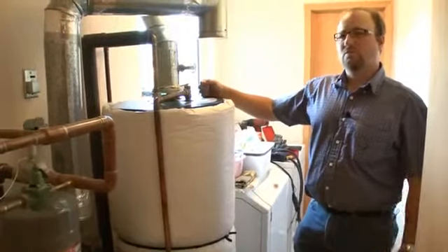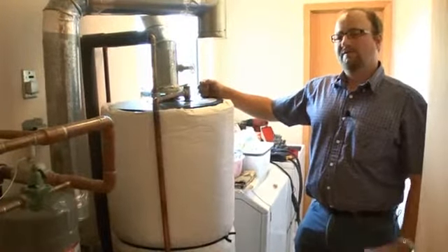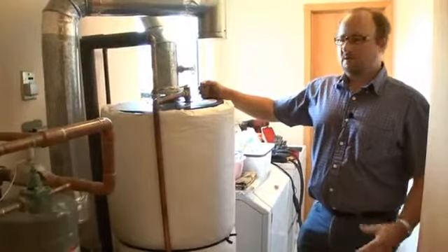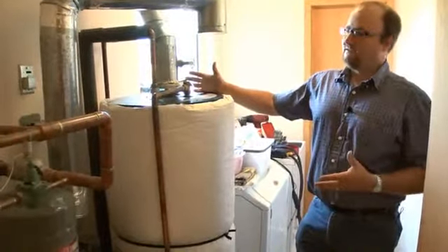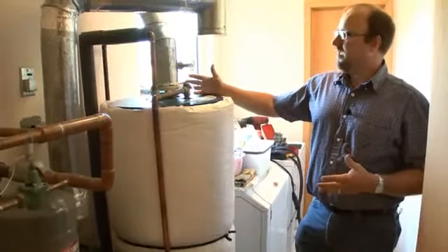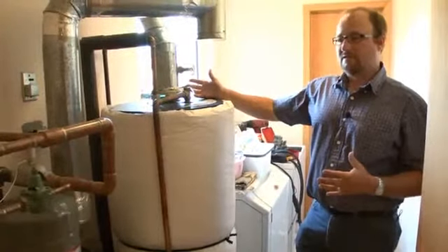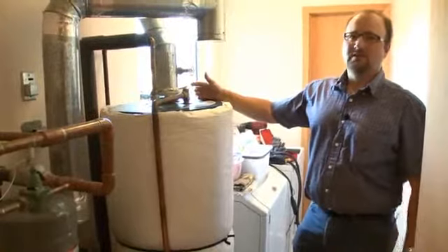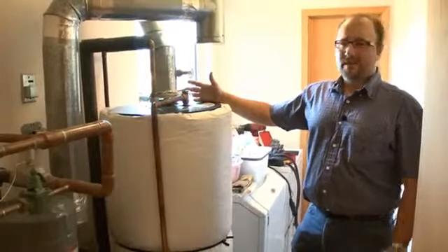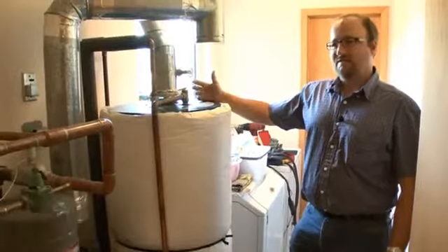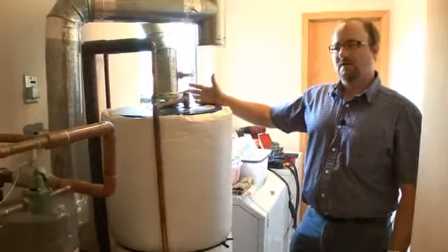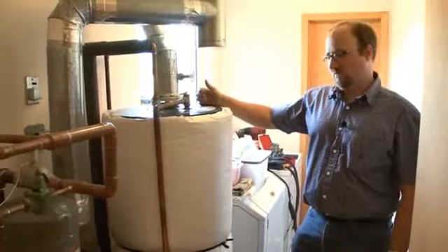So in order to move forward, what we have to do is turn off the fans, open the doors, and see if we have draft under the best of conditions. And if we do have draft under the best of conditions, then we can continue. If we don't have draft, then we cannot continue with our diagnostics. We would have to solve the problem before we could continue with further work.